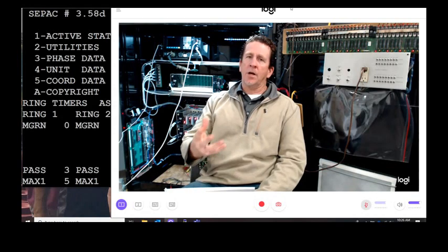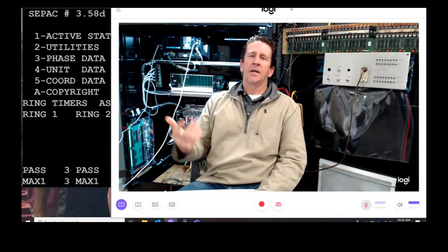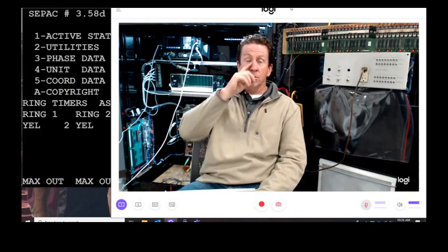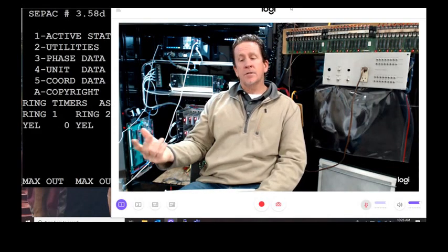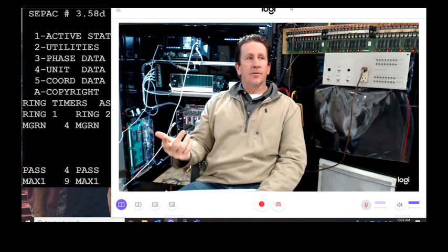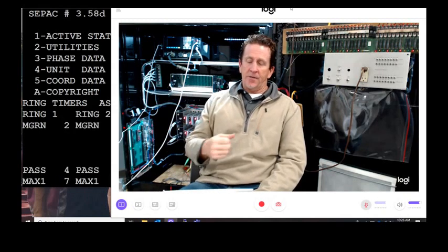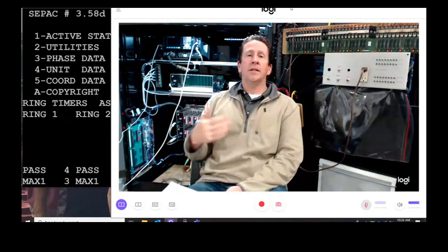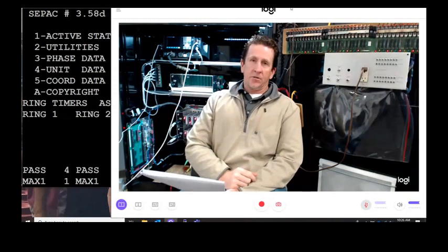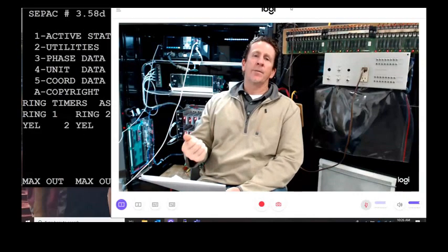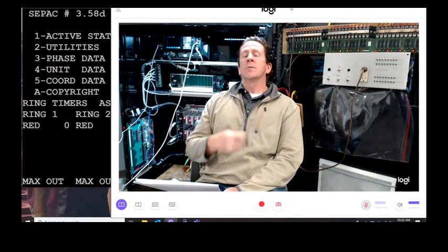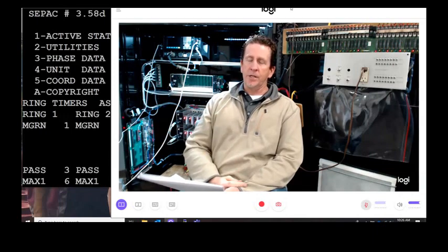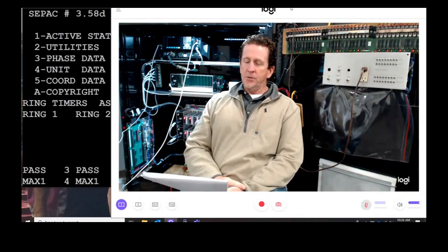The power supply, we refer to the auxiliary power supply that sits on the shelf. Typically, the older ones is a CPS 102. We now have CPS 105s, or you could have an EDI 250. Basically, they have an array of LEDs on the front of them. A lot of times I'll say, look at the power supply, make sure the LEDs are on. If the LEDs are out, they have fuses in there. It might be as simple as we'll replace the fuse. Sometimes you put the fuse back in, it blows instantly, then we know that there's a short in the power supply.